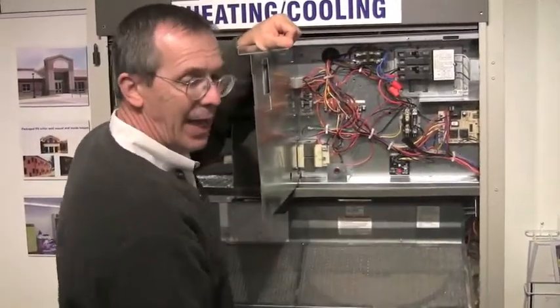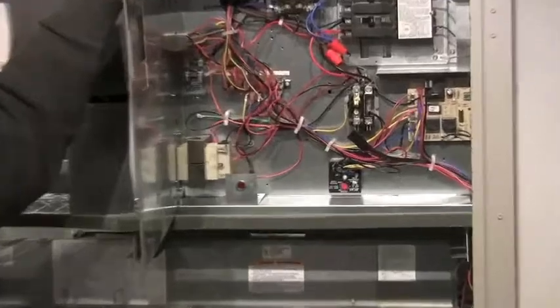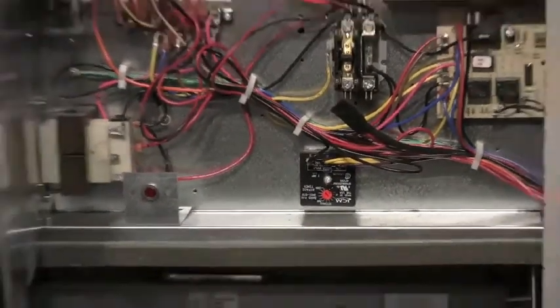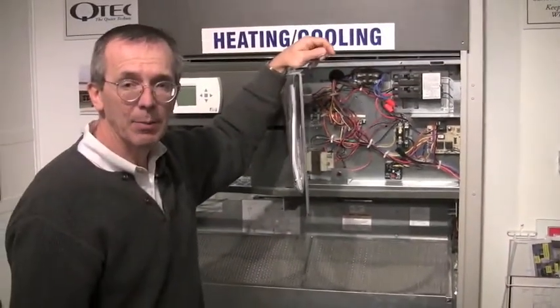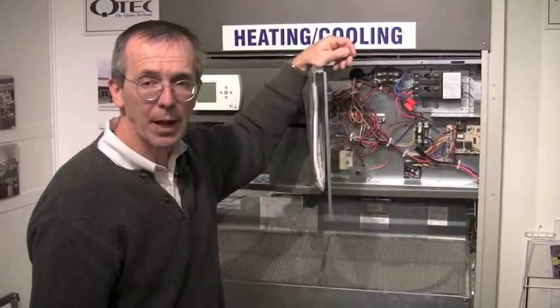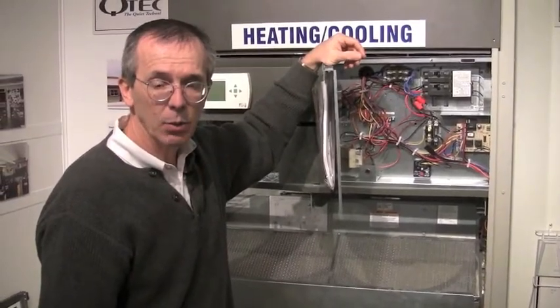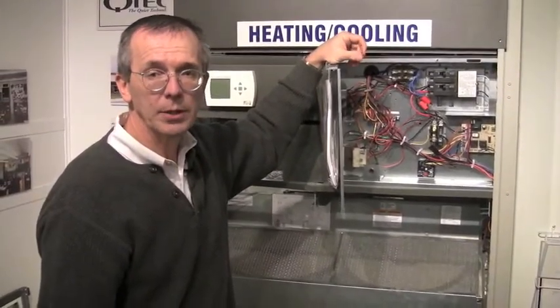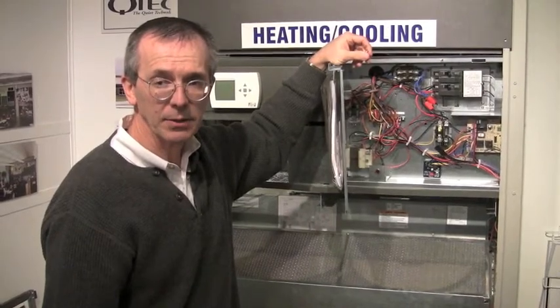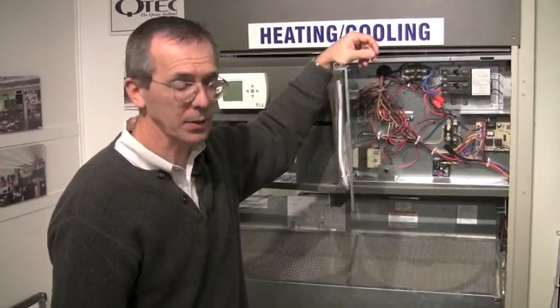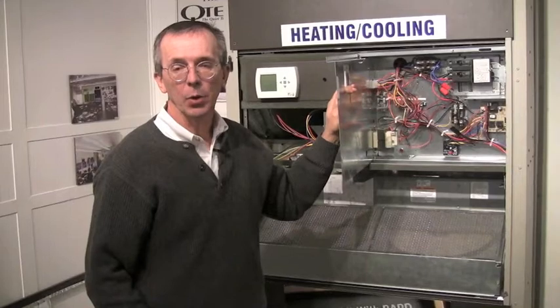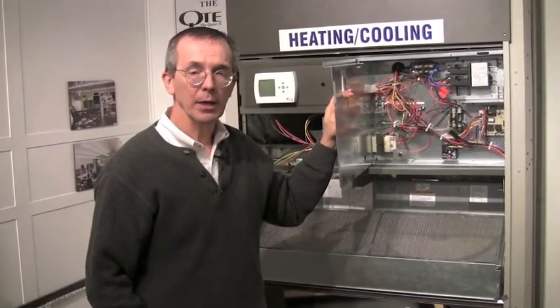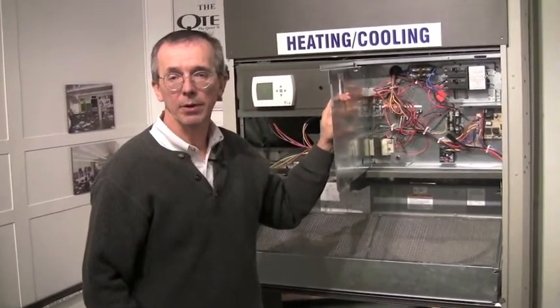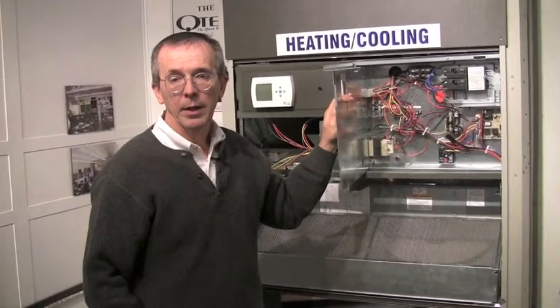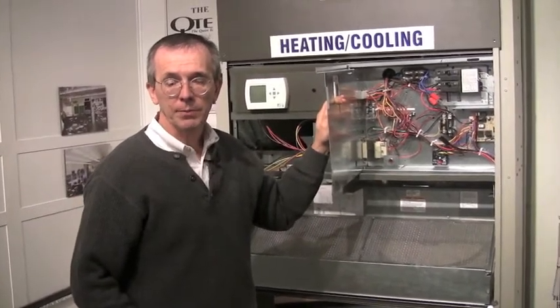This here is a timed bypass low pressure switch. On a cold start, the timer bypasses the low pressure switch for about 120 seconds. Once the unit builds up to pressure, after that 120 seconds, the low pressure switch is put back into the system. On all 3-phase equipment, whether it's the Bard Q-Tec or the Bard wall mounts or any of their packaged equipment, they have scroll compressors.